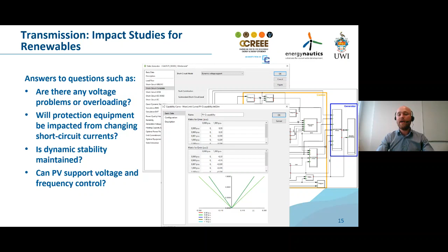A lot of times these studies will also inform you how your generators could contribute to the system, and that includes any renewable power plants. They are new to the system in many countries, but they can actually support it in terms of voltage and frequency control, and with this tool you can investigate this. Here are some visual examples from the software of different dynamic stability analyses we performed. You could, for example, look at frequency stability, checking if, after a certain contingency, maybe a generator dropping out, your frequency remains stable, and whether your primary response and primary reserves are able to contain the frequency to an acceptable level.